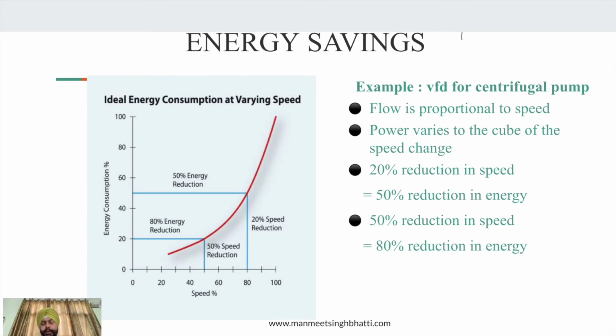So putting a VFD in the complete system gives you two things. First of all, it is going to control the amount of pressure which is required at your farthest end. So you can directly interlock: say you need a pressure at the farthest end of 7 bar, you can directly put a pressure transmitter over there, get that signal back to the VFD, and put it as a set point to that VFD that at this point you need a pressure of 7 bar.